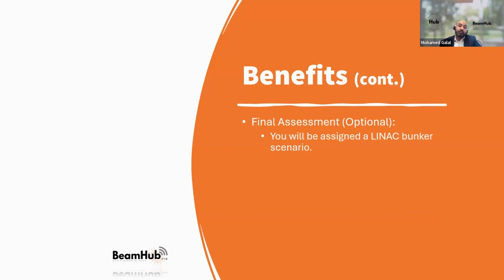It's sometimes all about the assumption, about your feeling about the situation. So you assume this can be like that. You assume this would be like that. Scatter angle or whatever, workload and use factor. Some people decide to use a 0.25 use factor in this direction, but some others don't. It's all about your experience and your point of view.